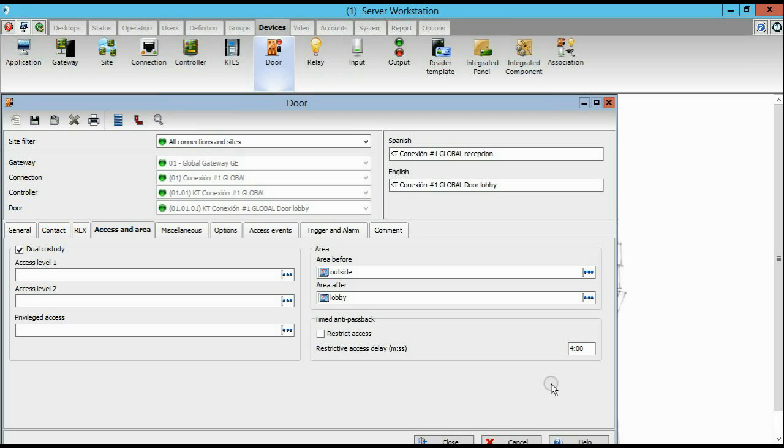You have to make sure your design is done so that those four doors are in an area, and if you have other doors on another controller, you will have to move those doors to the same controller in order to make sure the anti-pass back is working 100%. Of course, that works fine up to four doors. You can go up to 8 readers if you have a KT400 with in and out.